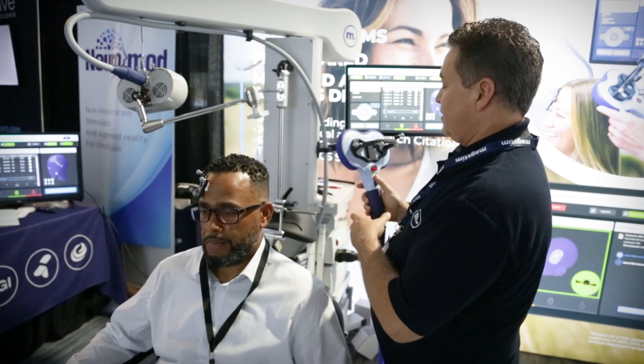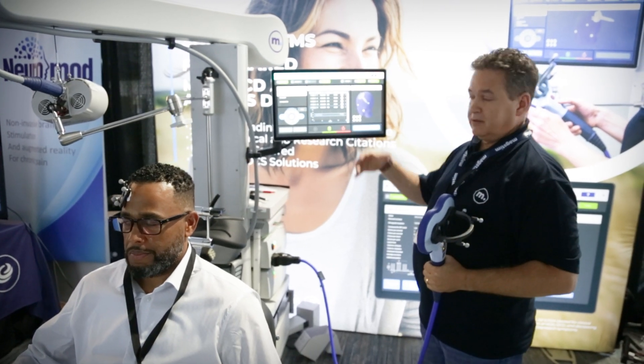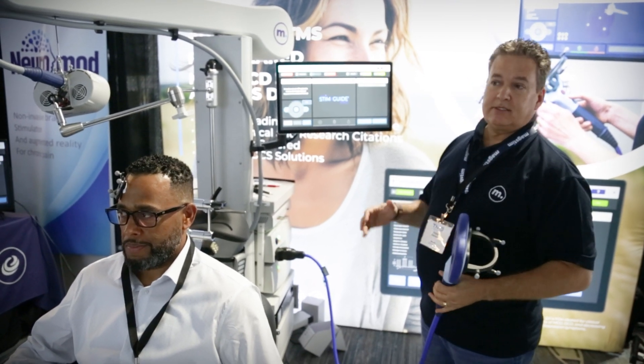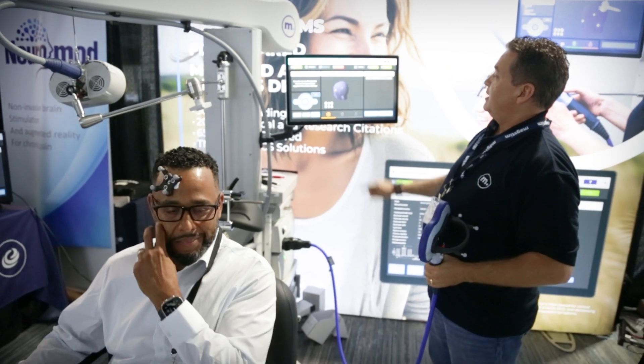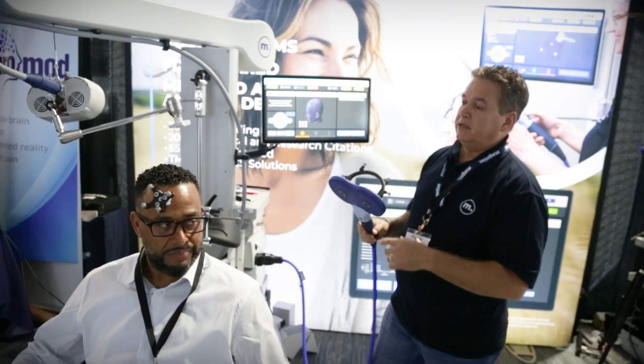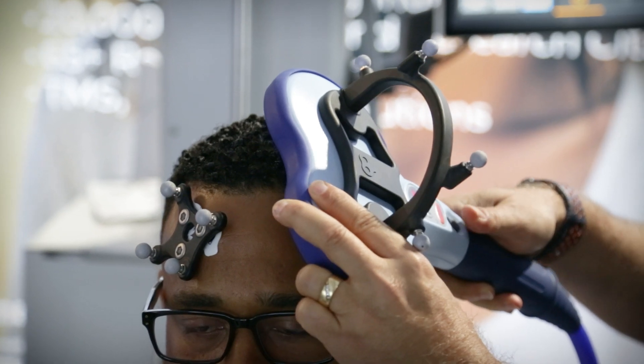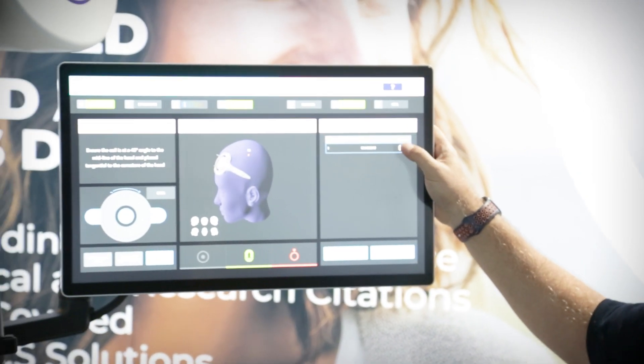Go ahead and make a fist. I'm going to call this his motor threshold right at 64. All I have to do is register that so the system knows the power to save. I'll hit next, and now it's going to guide me to the treatment location, which is defined as five and a half centimeters forward on the sagittal plane — that yellow cylinder right there. I put the coil up to that yellow cylinder and it's going to turn green. That's how I know I'm right on there. I stim one time and the map is done. That simple.